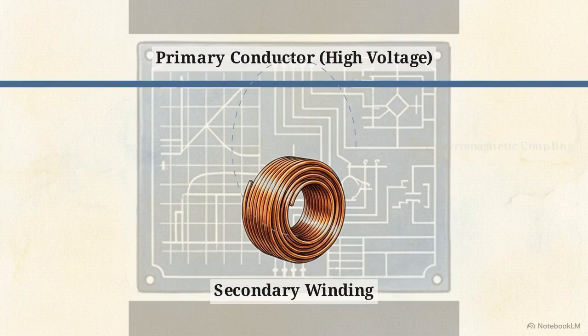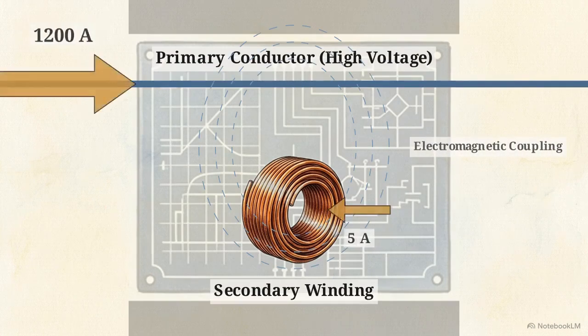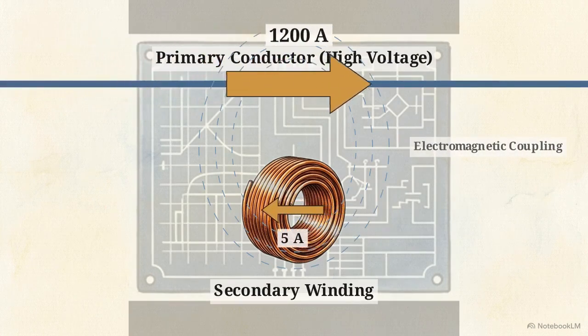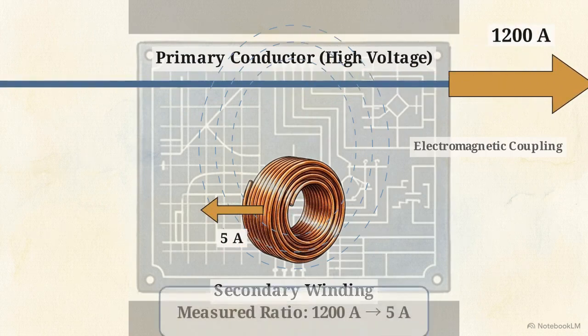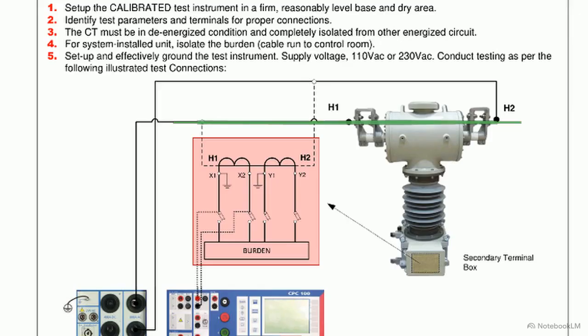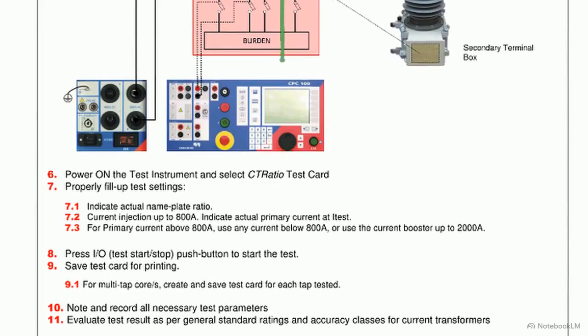Here, we measure the physical electromagnetic behavior by injecting a known primary current and verifying the exact secondary output. The Omicron CPC100 drives current through the primary H1 and H2 terminals. Simultaneously, its voltage sense leads monitor the resulting output across the secondary X1 and X2 terminals. Inside the software, the technician enters the expected nameplate parameters directly into the CTRatio test card, giving the instrument a benchmark for its pass-fail logic.